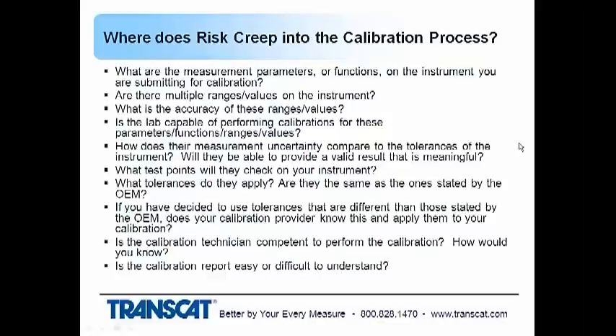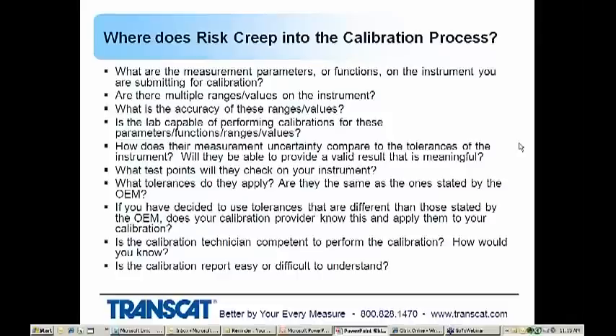So getting down to the tolerances that are applied in the calibration of your instrument, are those the same as the ones stated by the OEM? Or if you decided to change those tolerances for your purposes, does your calibration provider know that? And did they apply that to your calibration?